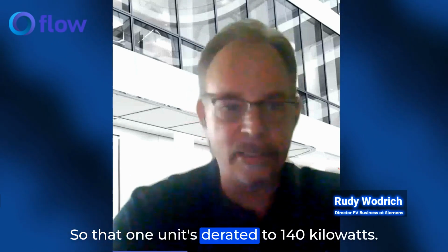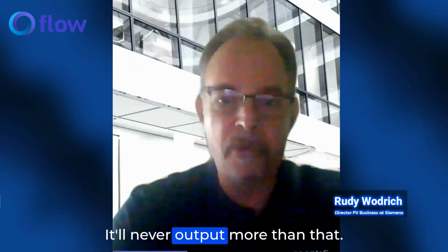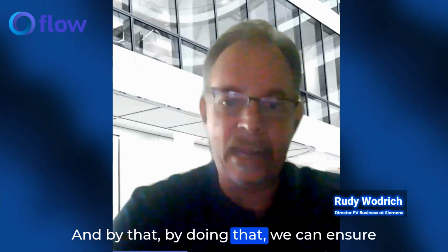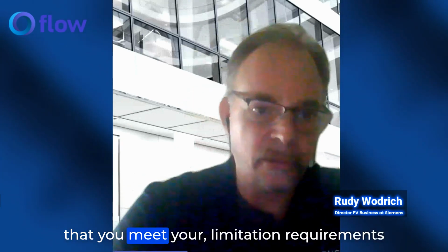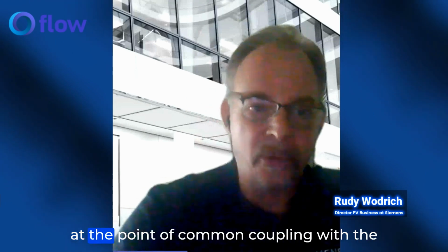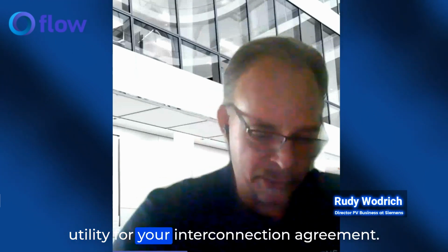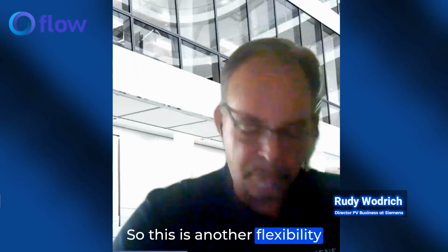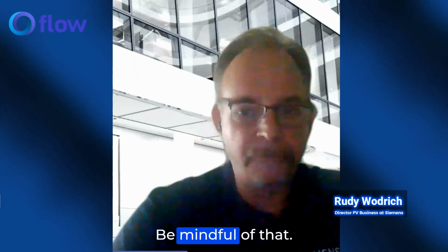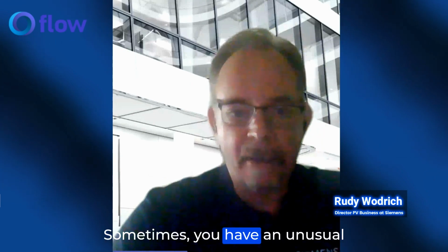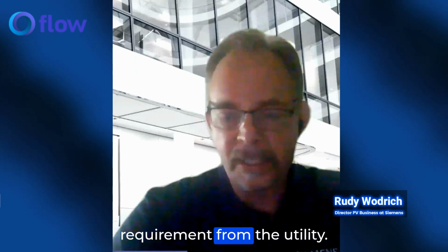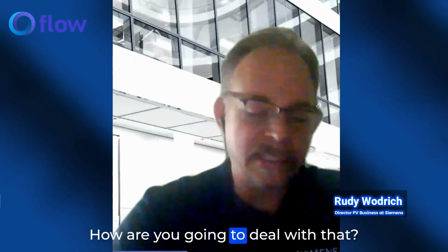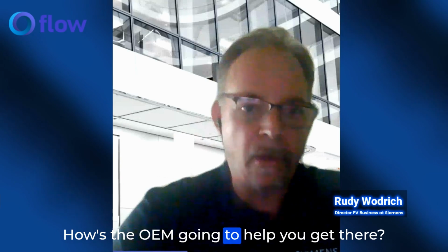So that one unit's derated to 140 kilowatts. It'll never output more than that. By doing that, we can ensure that you meet your limitation requirements at the point of common coupling with the utility for your interconnection agreement. So this is another flexibility thing that you have to be mindful of, that sometimes you have an unusual requirement from the utility. How are you going to deal with that? How's the OEM going to help you get there?